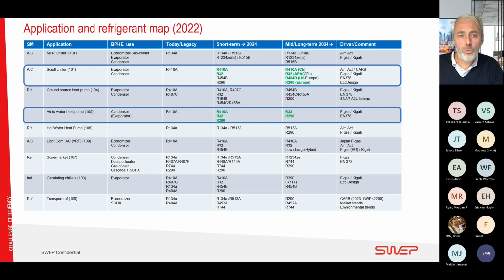Moving on to air-to-water heat pumps. Here the BPHE is typically used as a condenser in the monoblock system, and also as an evaporator during the defrosting sessions that take place. Up to now, also here, 410A has been the dominating refrigerant. But in the last years, there has been a quite obvious conversion to R32 and to R290. And we believe mid to long term, we will have R32 and R290 as the main refrigerants here. This is mainly a European system, so F-gas and Kigali are the regulations that drive the conversion, and we have the safety standard EN 378 and the substandards to this.